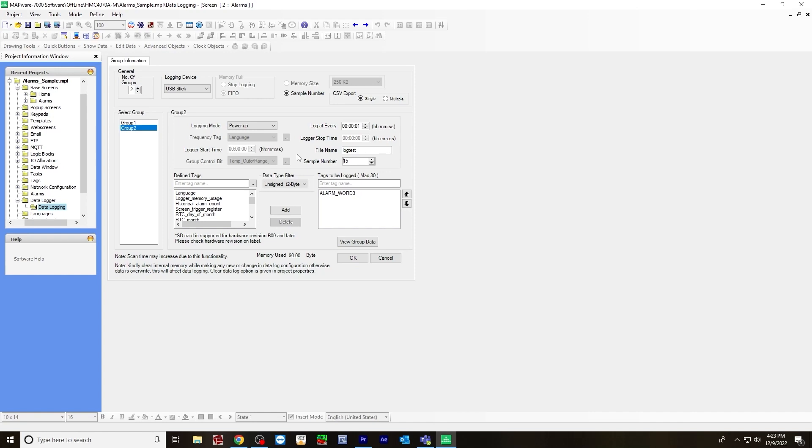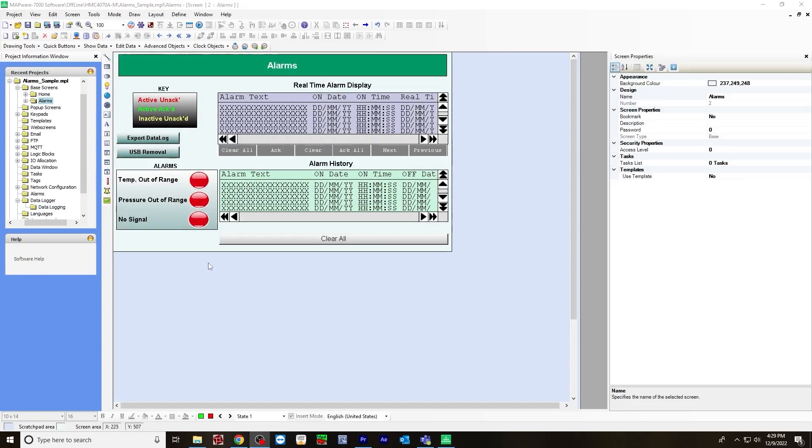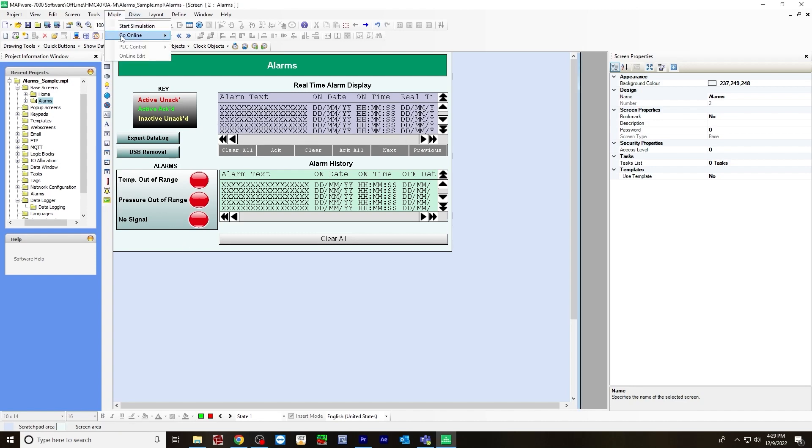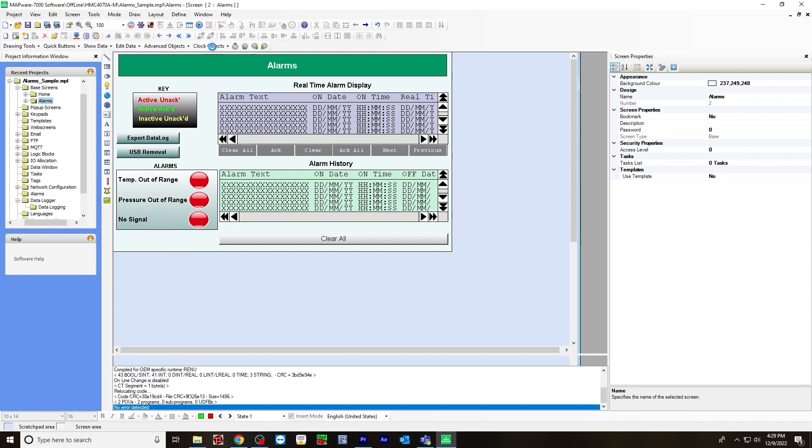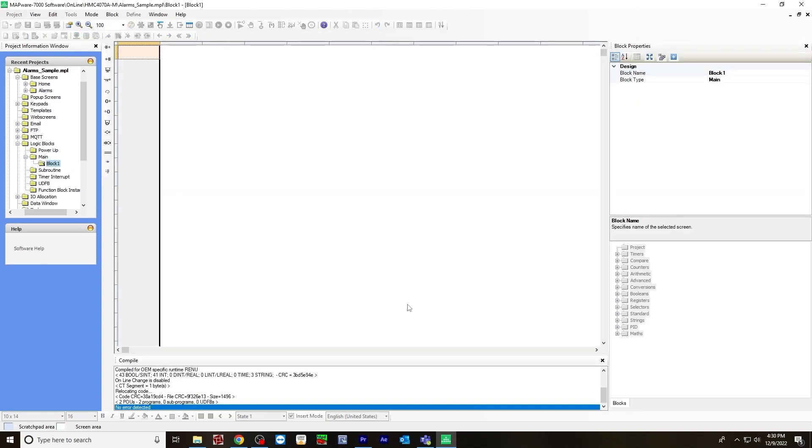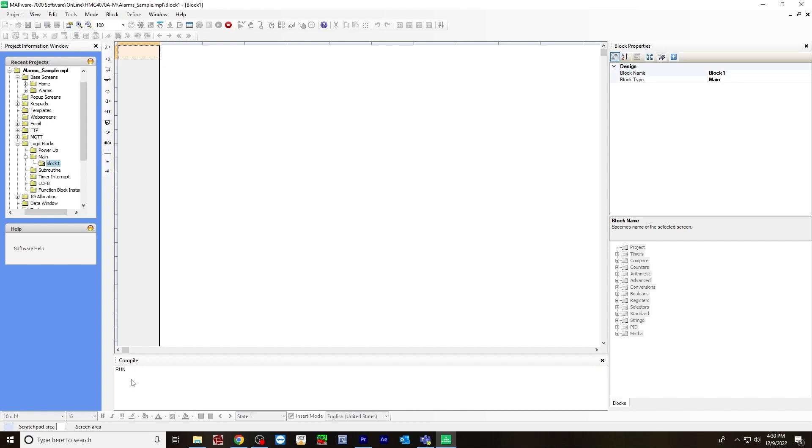Now that you have set up your base screen, your alarms, as well as your data logger, you are now ready to download and go online. To download, go to mode, go online with download. If you are downloading for the first time, make sure you have firmware checked off. In this case, I've already downloaded once, so I just need to have application checked off, hit download. It may take a few seconds for the HMC device to load the application. Once it does, in the compile window, it will say run. That's how you know you're online and it's working properly.